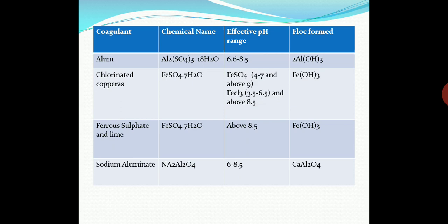For that reason, for alum to be more effective, the pH of water should be in the range of 6.5 to 8.5. The dosage varies. If the pH is in the range of 6.5 to 8.5, the alum is dissolved in a certain amount of water and applied to impure water. The dose of alum varies between 10 to 30 mg per liter of water.